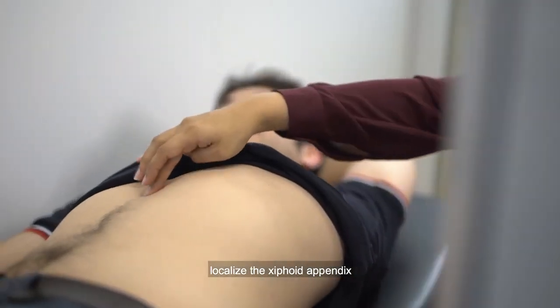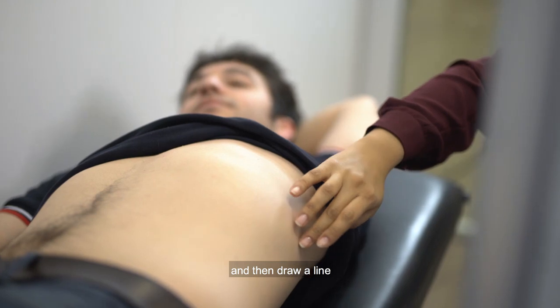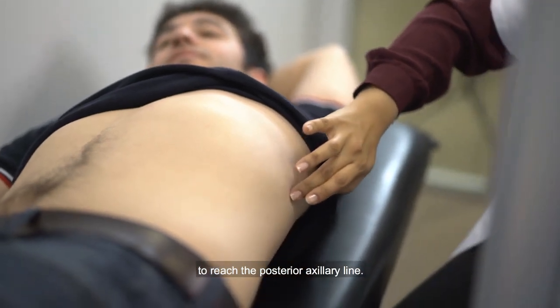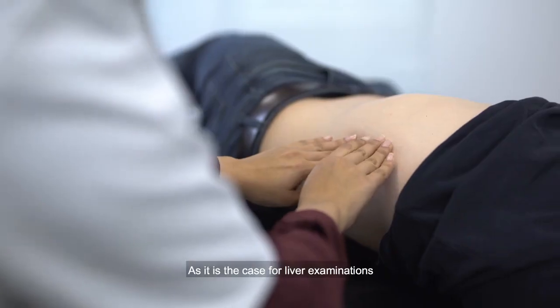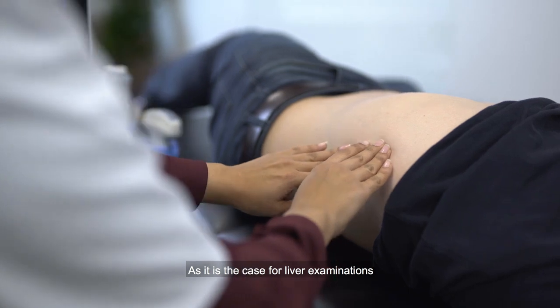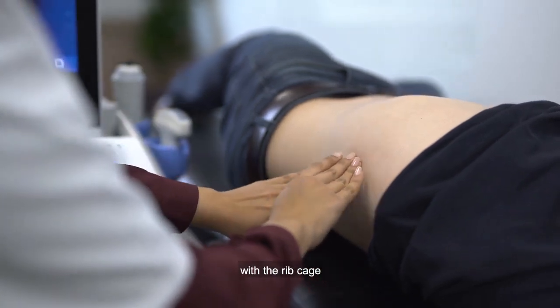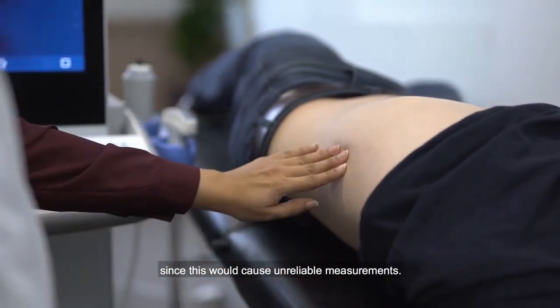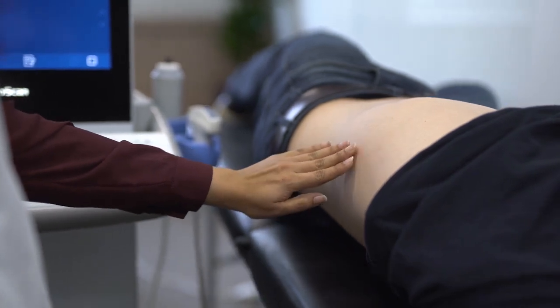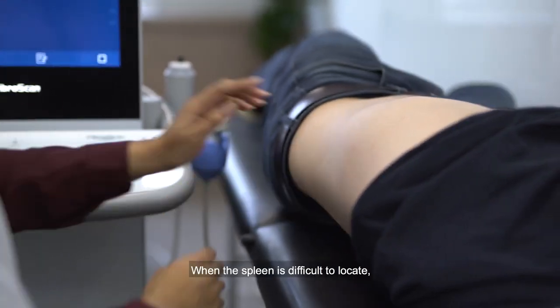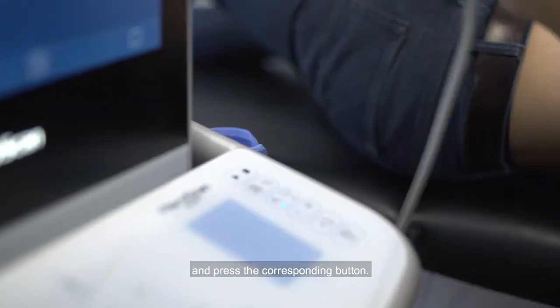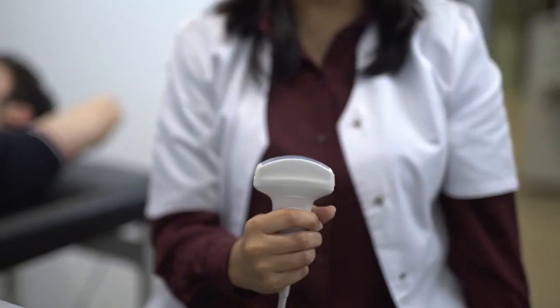Localize the xiphoid appendix just below the sternum and then draw a line to reach the posterior axillary line. As is the case for liver examinations, make sure to avoid any contact with the rib cage since this would cause unreliable measurements. When the spleen is difficult to locate, take the guidance probe and press the corresponding button.